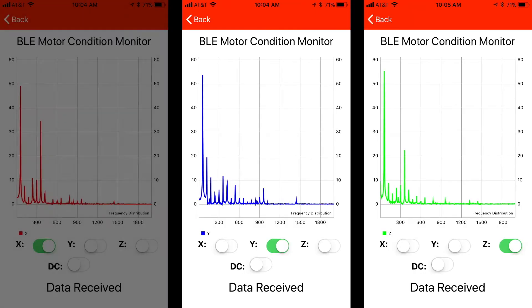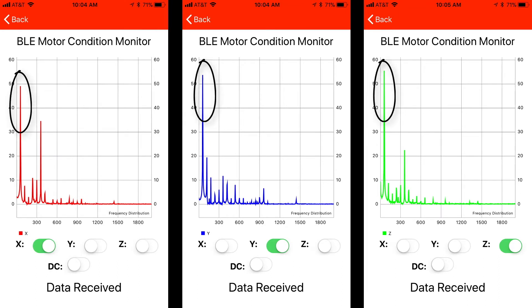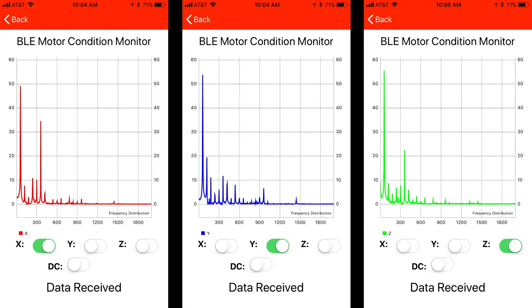As can be seen in the frequency spectrum for the X, Y, and Z axes, the fundamental component of the vibration is at 60 Hz. However, we also see substantial amplitude for the fifth harmonic on the X and Z plots, indicating some level of vibration outside the smooth operation of the motor.